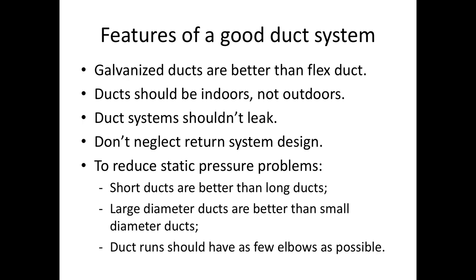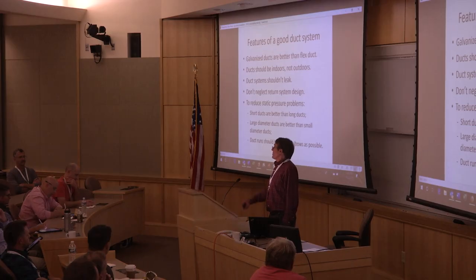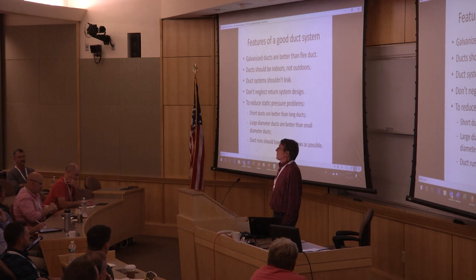Don't neglect return system design. For years people just didn't care about it. They'd put a big register in the hallway wall and run some 12 by 12 duct back to the furnace and call it good. So when you're in your bedroom at night and close the door, the room gets pressurized by the supply system, and there's no way for return air to go from that closed-door bedroom back to the furnace. You could undercut the door, but the math is bad on door undercuts. You could do a jump duct or transfer duct, which can work but have noise transmission problems. Or you could have the Cadillac system with a return grill in every room. But you have to think it through—you can't not know how the air is getting from your bedroom back to the furnace. It's got to have a path, and as a designer you need to be able to answer that question.